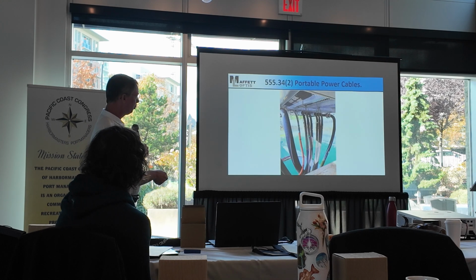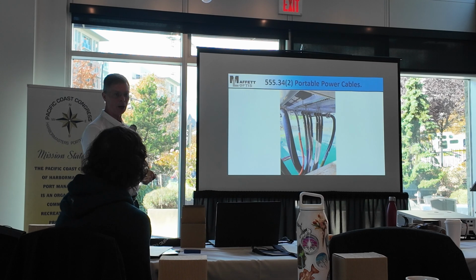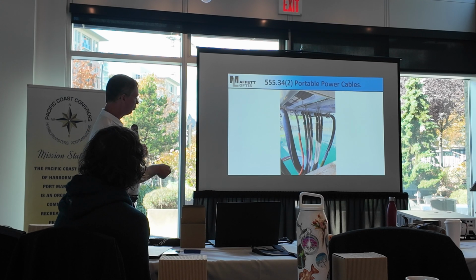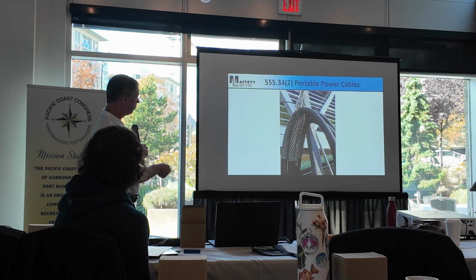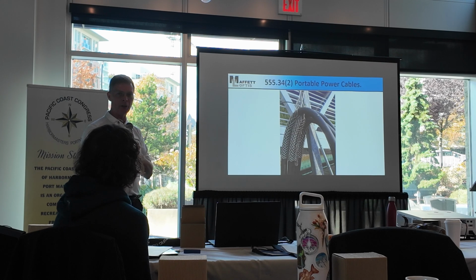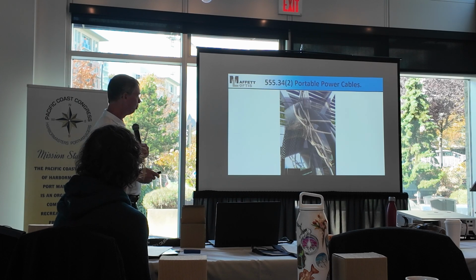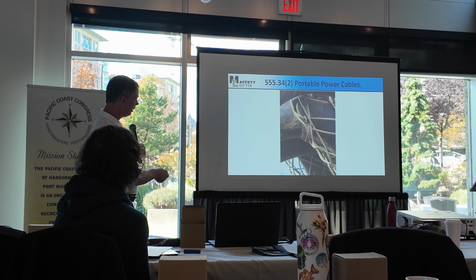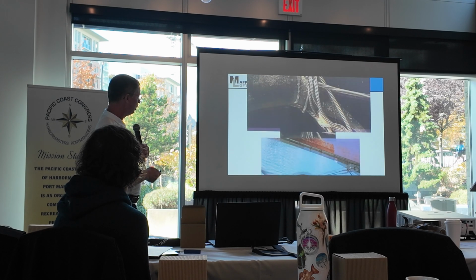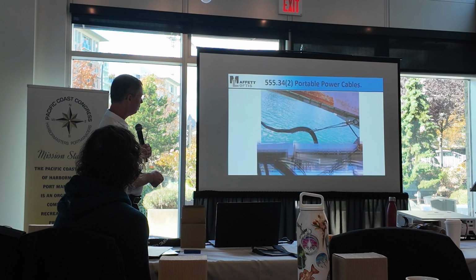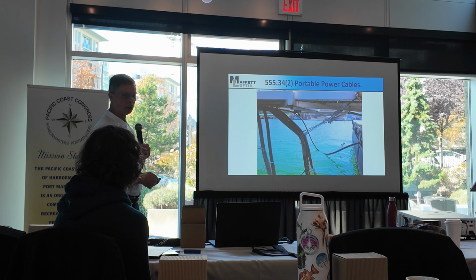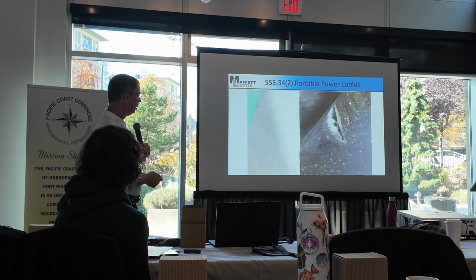And then Kellems grips, always make sure your Kellems grips are straight down, right? Because that's how they're designed, so it grips the cable. Do not let it all be supported right there, because these cables out here are all supported with that one little 1/8" strand of metal. Don't let this happen because it'll damage your cables constantly. See how tight that band is right there? This is terrible. That's not the way you support your cables.